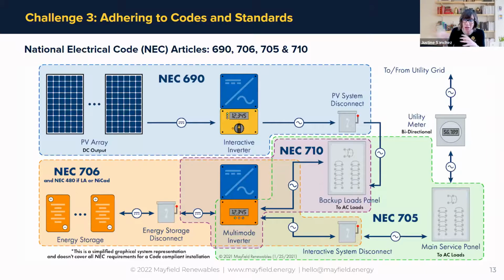That's historically for standby generators. But you might look at this as an optional standby system more so than a standalone system, even though there's code language and pointers within 706 that send you to 710 for the rules of when you're in standby mode and what has to happen there as far as capacity, automatic transfer switching, and even how you interconnect with a particular breaker that's not marked line and load, if it's a load side connection. All kinds of little rules in 710, not a lot, but definitely some.